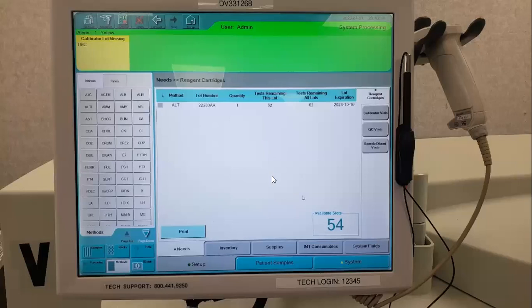All right, before the machine goes into downtime, we'll also go to the setup and needs. This will bring up any flex packs that we might need shortly. So this reagent here, there's only one on the machine, and there's only 62 tests remaining on this lot. And the lot expiration is in October. So this lot will be good to stay on the machine. It will just get used up fairly quickly. So if this is the only one that's low, we don't need to worry about putting any more flex packs on.